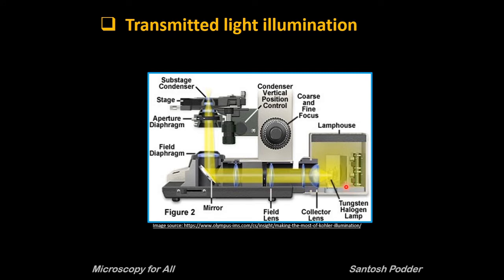This is a cross section of light illumination at the base of an upright microscope. Light emitted from the tungsten filament passes through the collector lens, which is near the lamp house, and then through another lens called the field lens, which is near the field diaphragm. Focused light leaving the field lens is reflected by a mirror positioned at 45 degrees to the light path and passes through the field diaphragm and into the sub-stage condenser. The collector lens and field lens help to focus the image of the lamp filament onto the condenser aperture.